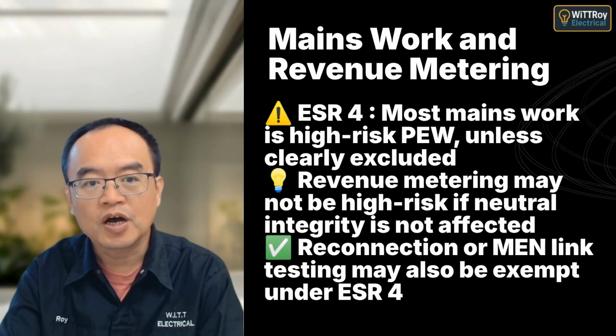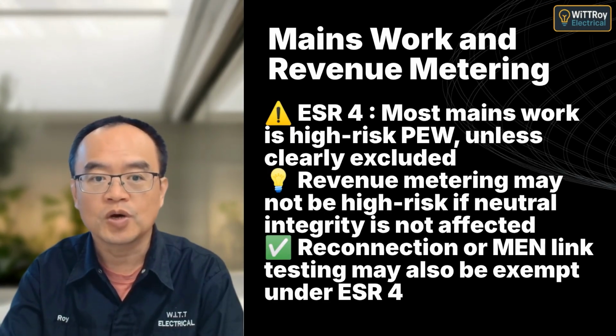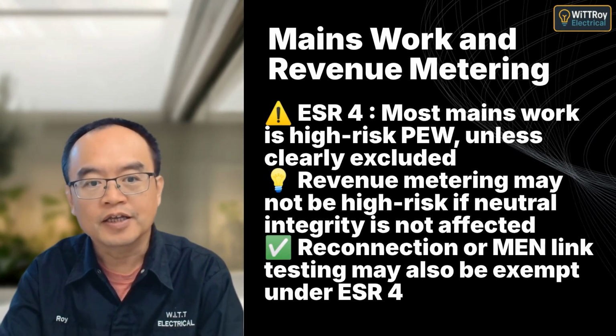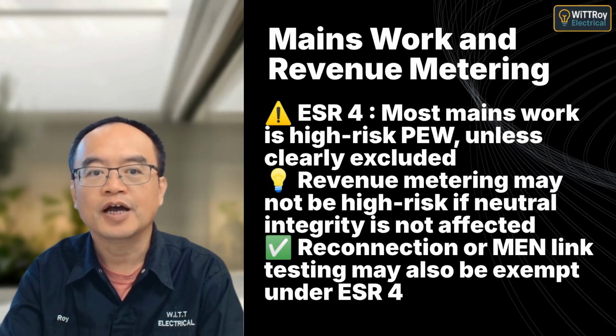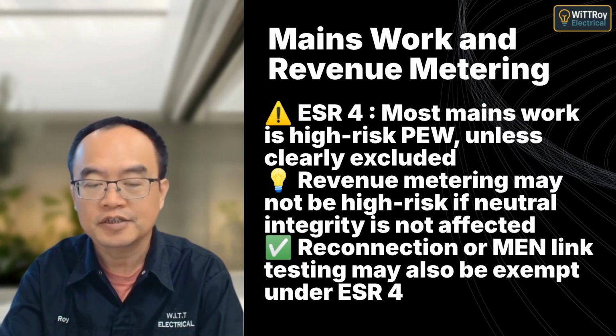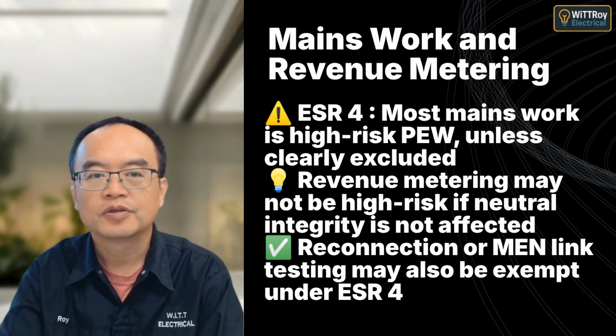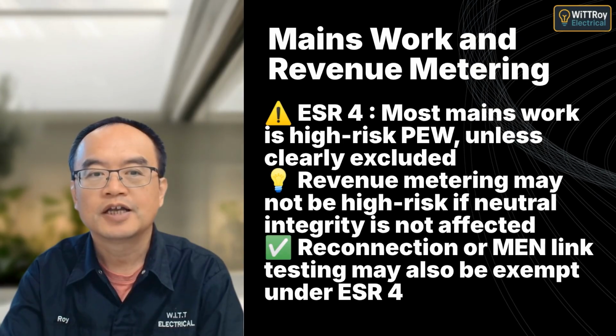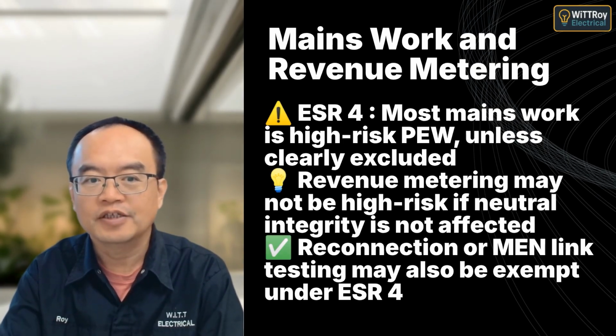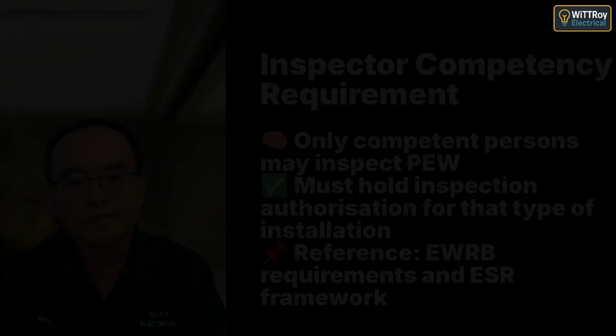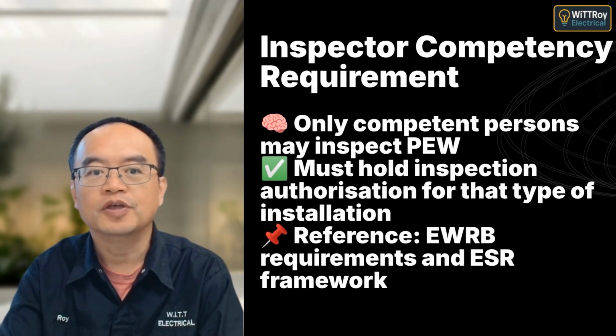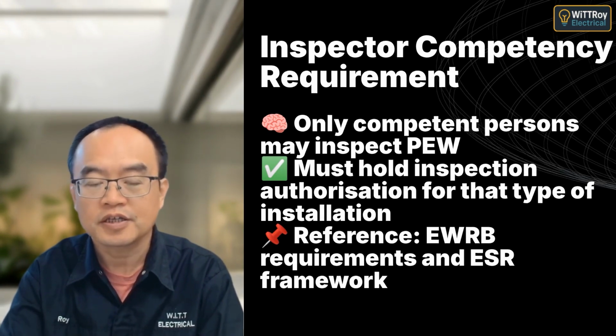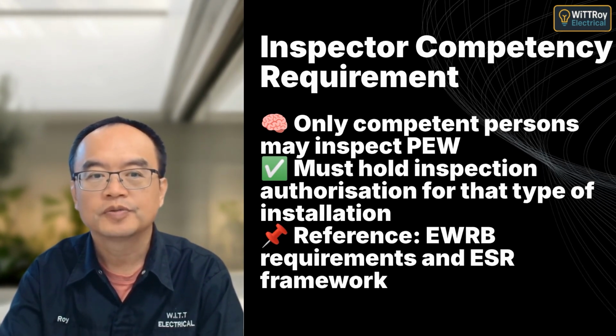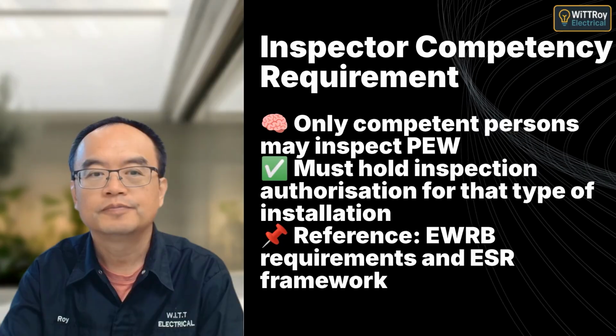Mains work is usually high-risk prescribed electrical work and requires inspection, but under ESR 4, some exceptions apply, like revenue meter installation, as long as it does not affect the integrity of the neutral or transpose active and neutral conductors. Similarly, replacing the MEN link for testing may also be exempt. An inspector may only inspect PEW if they are competent and authorized for that type of work. This ensures the inspection is valid, safe, and compliant.